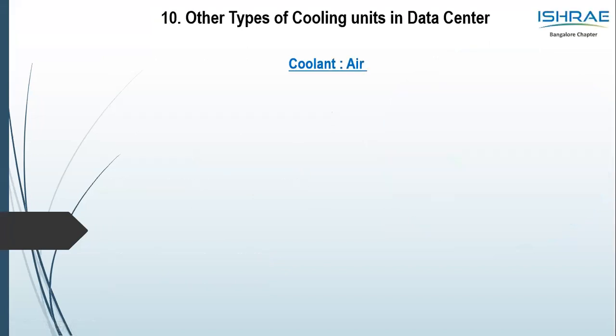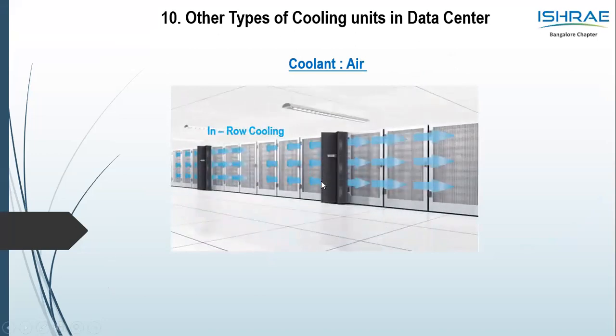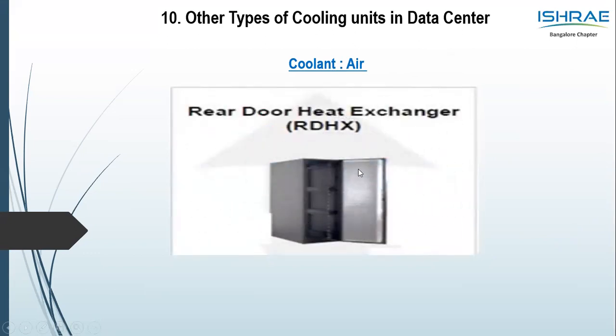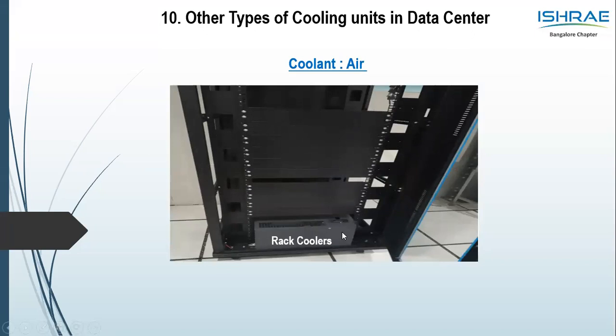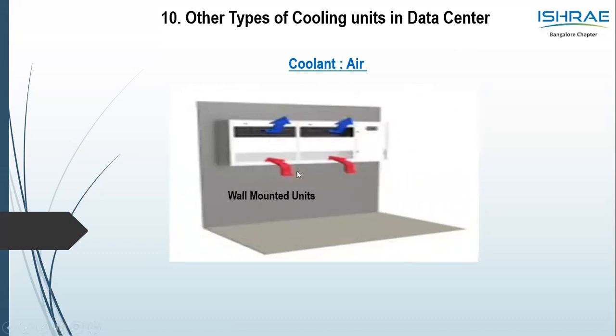To kind of summarize other type of cooling units which goes into the DC space, let's see a coolant as air. Number one is the in-row. Apart from the traditional unit what we saw, we also see in-row units which are kept in-row along with the neighboring racks, and the coolant is air. We also find the rear door heat exchanger, which has a heat exchanger on the backside of the rack, and the chilled water or DX is passed on to it. Then you have the rack cooler, where the small unit 1 TR or 2 TR is placed within the unit down or side, and it cools each of the dedicated rack only. And then we have the wall mounted, which goes into the DX or connected to the chilled water. Again, a small server room application, but different types of cooling units, what we have seen in various applications of server room or data center.